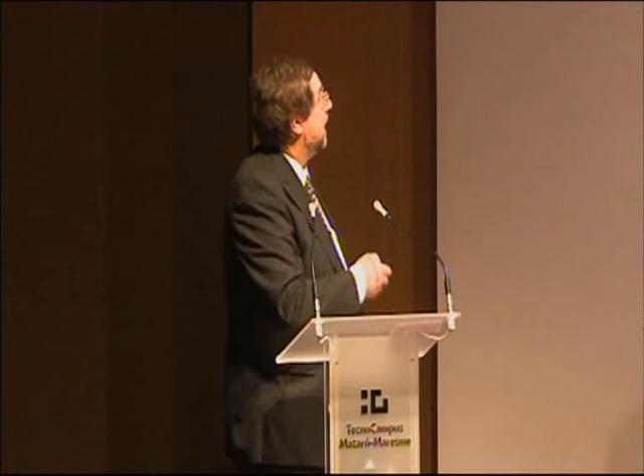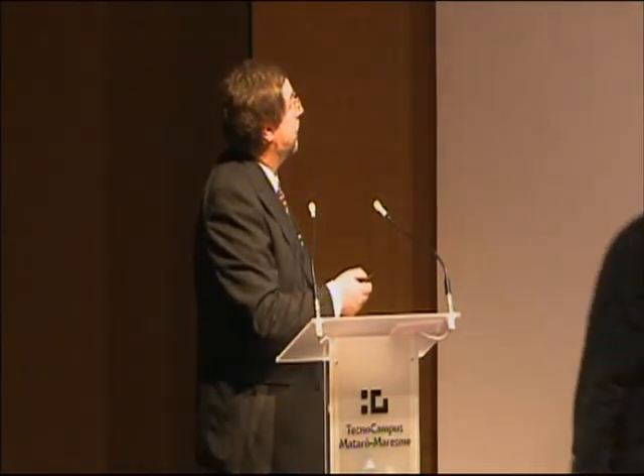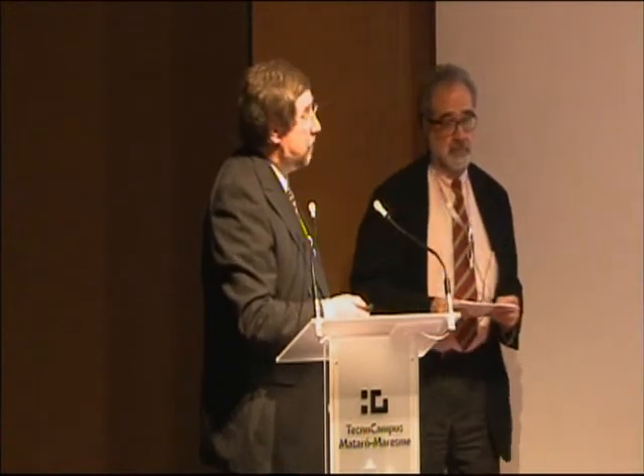Okay. If you look at the picture from the beginning for the BAT, if we have fulfilled the BAT criteria with this system and retrofitting wet and semi-wet scrubbers to the system, we can say yes, the absorption rate is still working really well. The availability is really high. We guarantee over 95%. It's no problem.